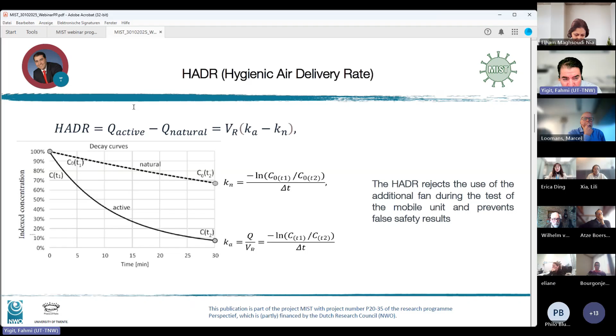And on the right side, you have a device which has a much lower fan capacity, but a much better flow characteristic. So the main message here is, one should focus on the flow characteristics, the fluid dynamics of a device, instead of the capacity of the ventilator or the unit itself alone. And how do we suggest to test it? You put it in a room, you wait 30 minutes after you created a base contamination level. You have a natural decay. You repeat the test again with the active device, the mobile cleaner, but without an additional fan like the CADR test. So the device itself should do everything. And from the difference between the natural and active decay, you can derive the hygienic air delivery rate.